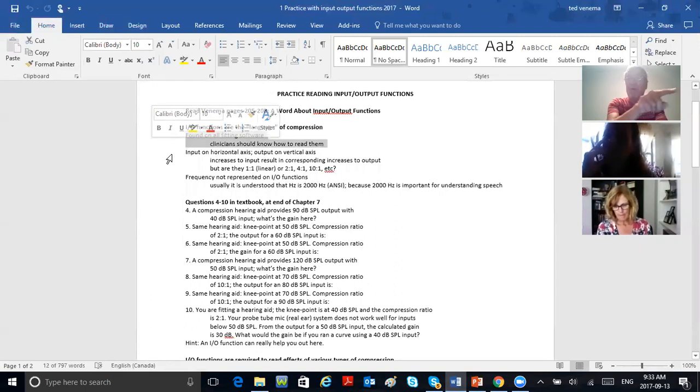On those, the horizontal axis is frequency and the vertical axis is amplitude, and you're looking at what the hearing aid is doing, basically a spectrum. That's mostly what you're doing, and that's what you'll see on hearing aid specs: the gain and the maximum power output. You're not usually working directly with input-output functions. You'll see them if you uncover them in the software. They're usually buried as a second layer, more for nerds, okay? But you still have to kind of know what they are.